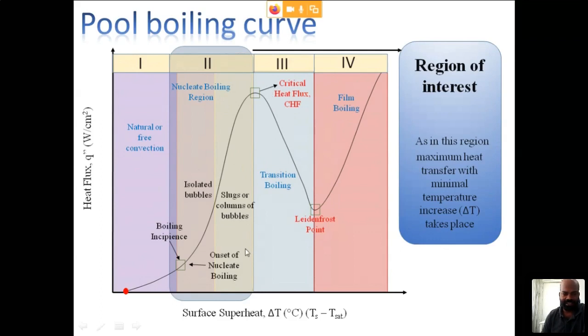The onset of nucleate boiling and the heat transfer coefficient are performance parameters giving the measure of system performance, but critical heat flux is not a performance parameter, it's a safety parameter. This is the critical point above which the system should not or cannot be operated, because above it, burning or system failure will take place.